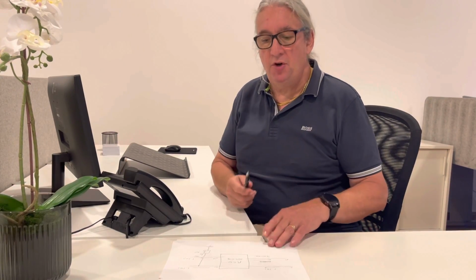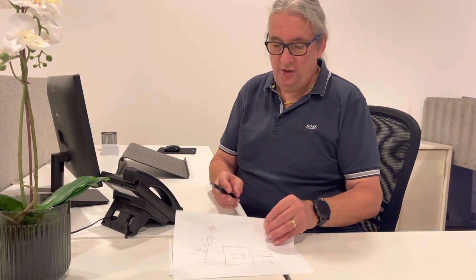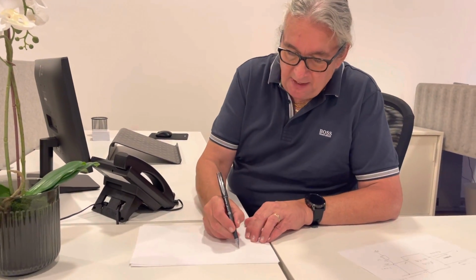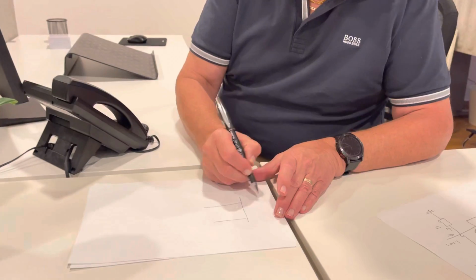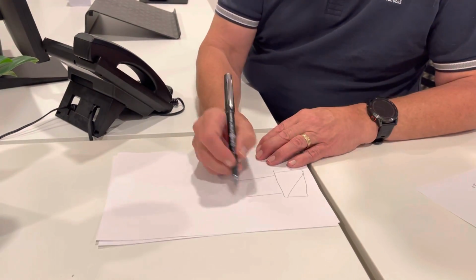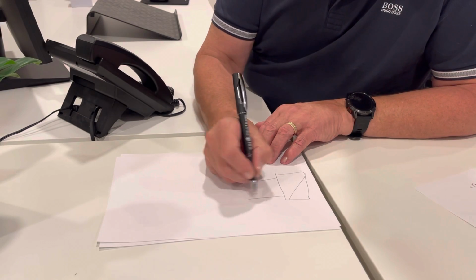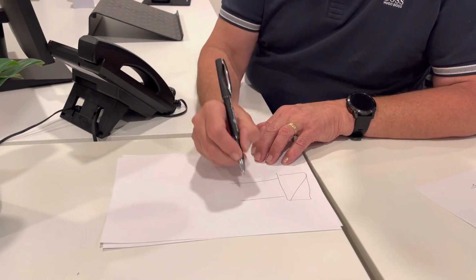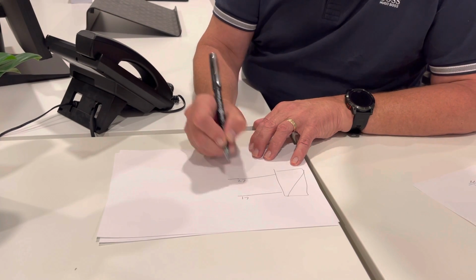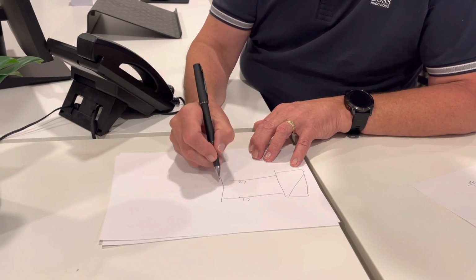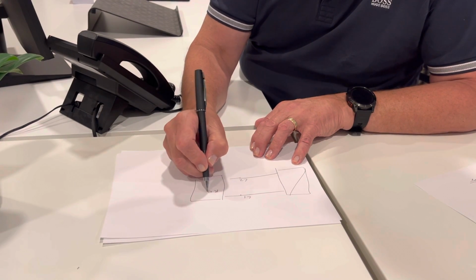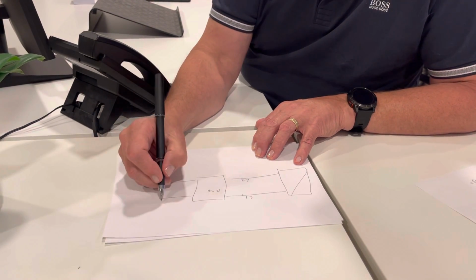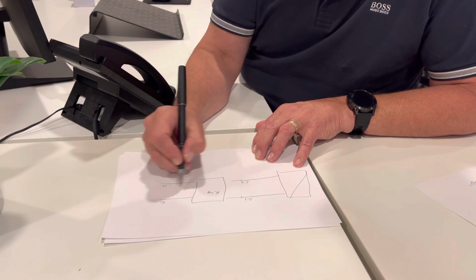So the reason the power goes into an inverter and then coming out of the inverter, we also put an RCD. Now, when it comes out of the inverter, the RCD will not function. It can't function. So the problem is, when the power comes out of an inverter, and this is my inverter here, I haven't got a live and neutral. I basically got 2 outputs, and I can call it L1 and L2. They come out, I put them into an RCD here, and I'll call one of them live and one of them neutral, and this is my load.